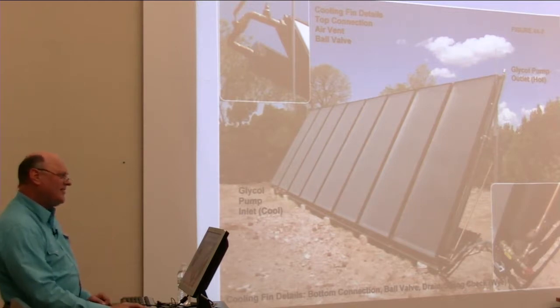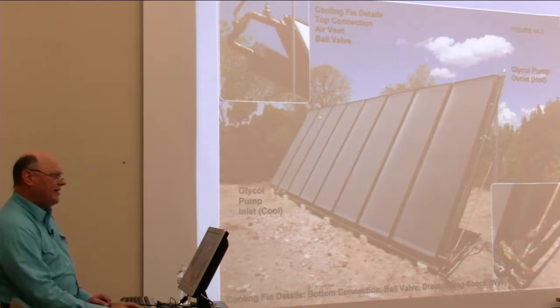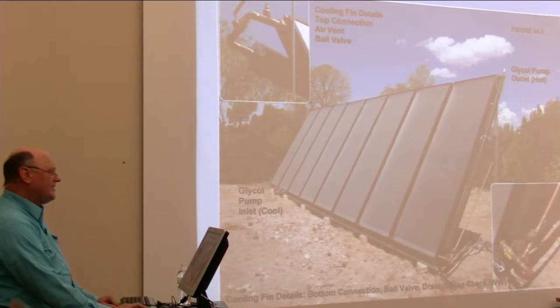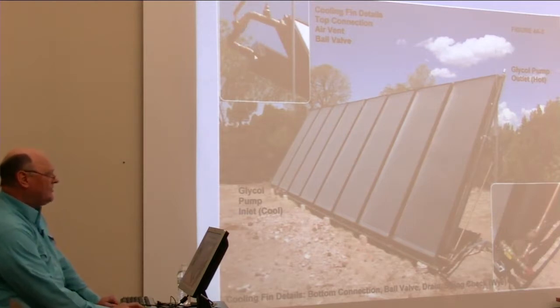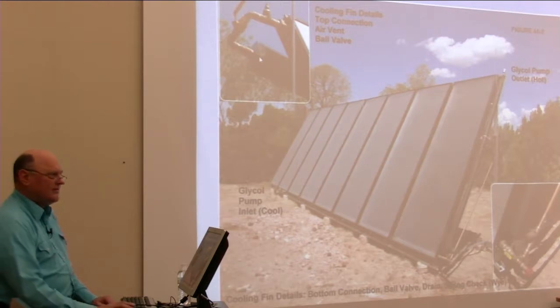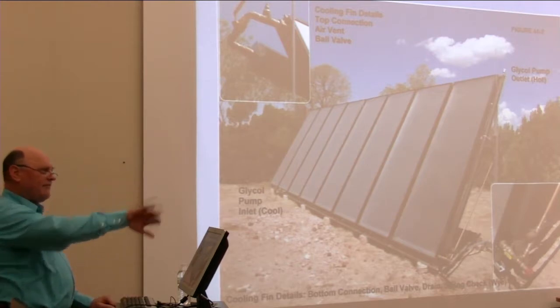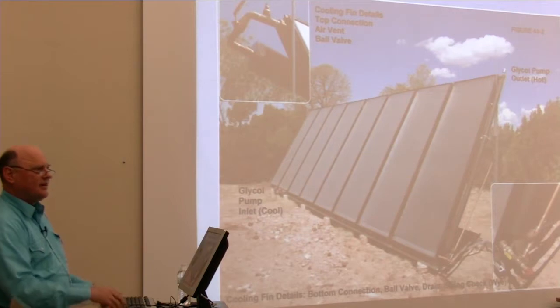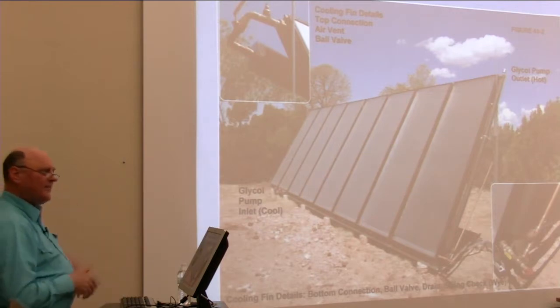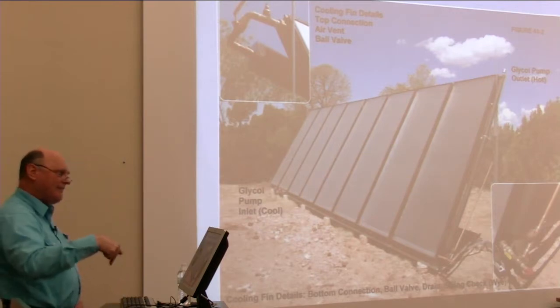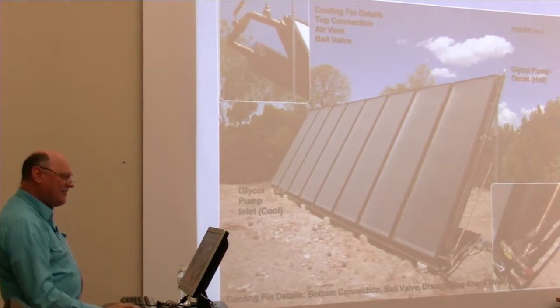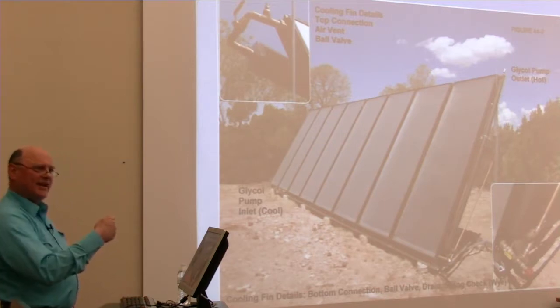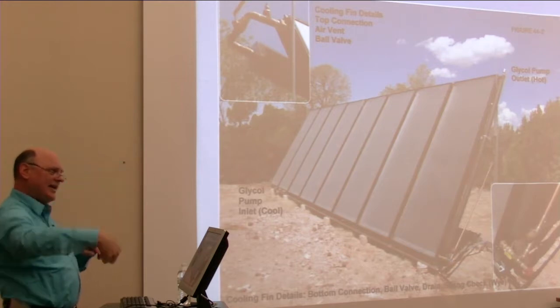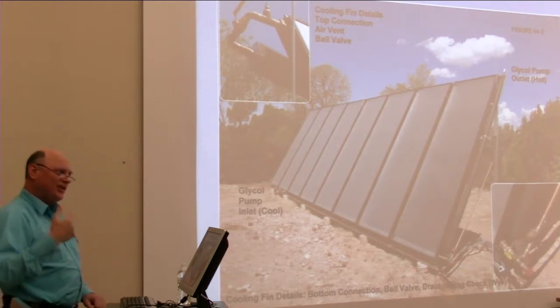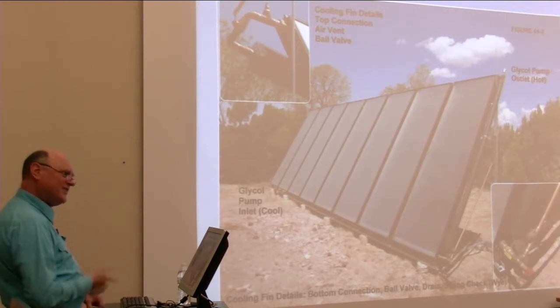So where does it go? Well, we've added a connection to the opposite corner over here. So it has to go out the opposite corner, and what's waiting for it at this corner? Cooling fins. So it rises, pushes itself into the cooling fins, and the cooling fins start giving off its heat to the air. It cools, becomes more dense, and drops. And it drops down to the opposite corner and goes back into the collector to get heated again and cooled again. So it's a closed loop thermosiphon self-cooling system.